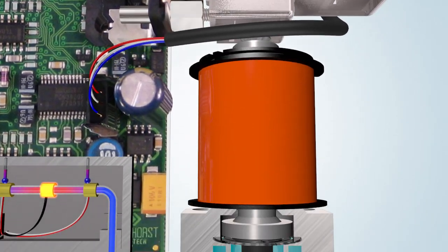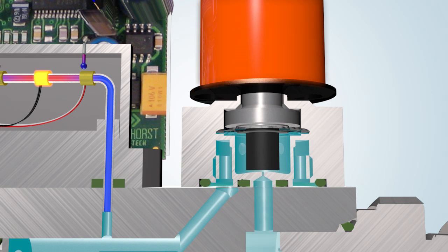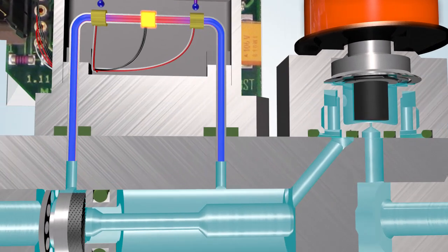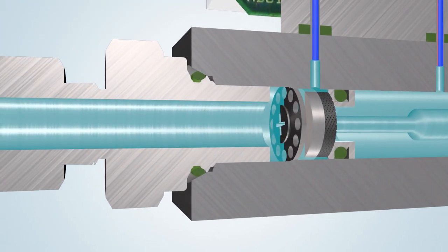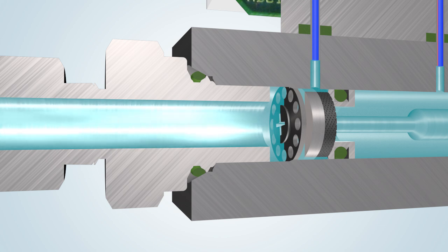The electromagnetic coil exerts a force on the magnetic plunger holder. This force is in balance with the linear spring that normally keeps the control valve closed. If the plunger comes free of the orifice, the result is a flow through the instrument.